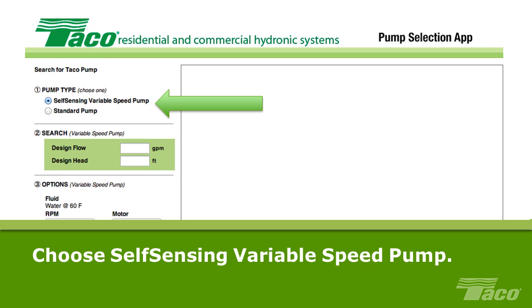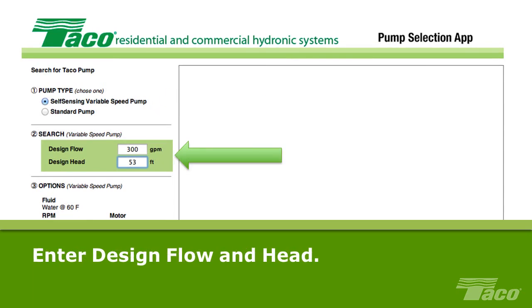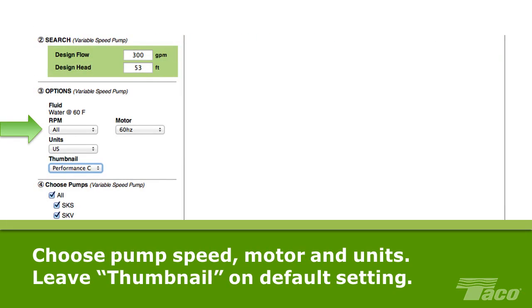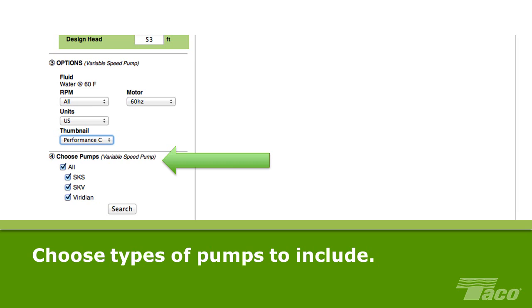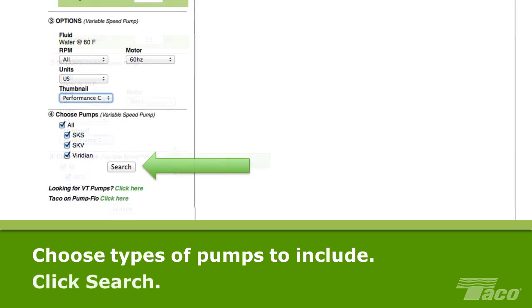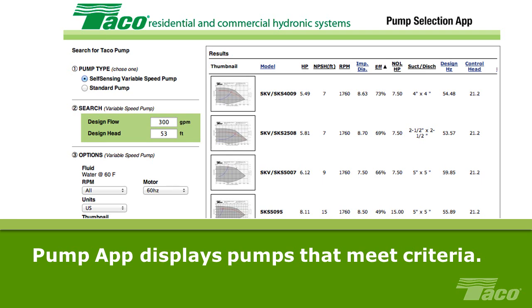Choose Self-Sensing Variable Speed Pump. Then enter the design flow and design head. We'll enter the values from our sample system, 300 gallons per minute at 53 feet. Choose the various options available for pump speed, motor, and units of measurement. Leave thumbnail on the default setting of performance curve. Next, choose the types of Taco variable speed pumps to include in your search. Then click Search. The Pump app displays the pumps that meet your performance criteria.